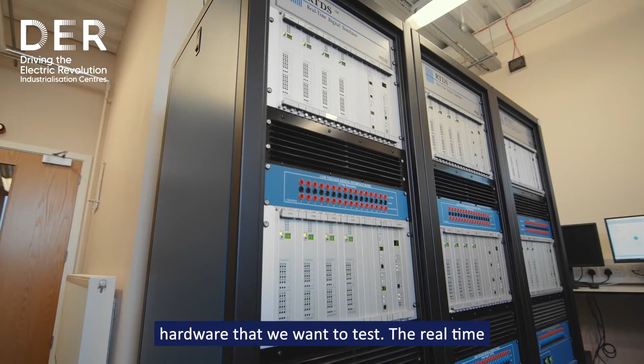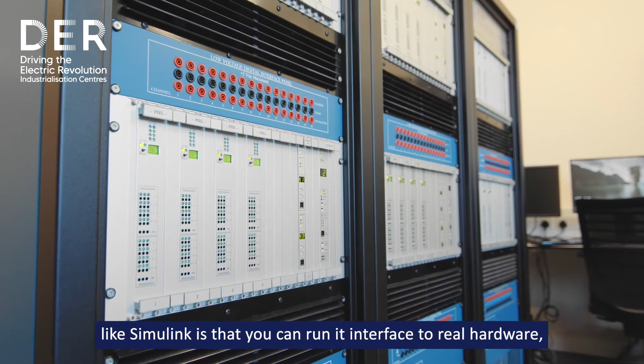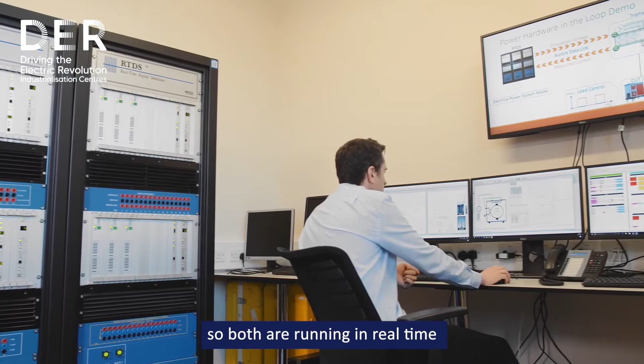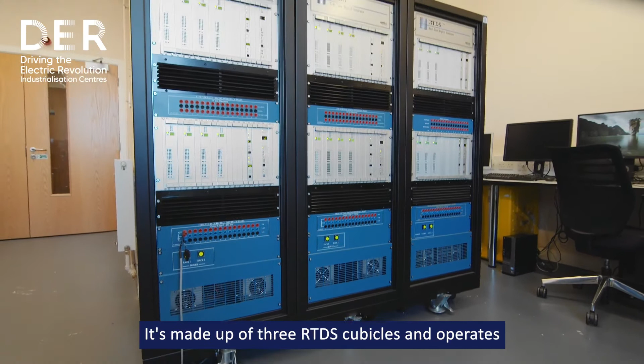The real-time digital simulator is a unique platform, and the 2 key advantages with our real-time simulator over offline simulations like Simulink is that you can run it interfaced to real hardware, so both are running in real time, and also that the development can potentially be quicker. It's made up of 3 RTDS cubicles, and it operates in both long time step simulation mode, which is 50 microseconds, used for power system simulation, and also a short time step mode, used for power electronic switching based applications, which can go right down to 2 or 3 microseconds.